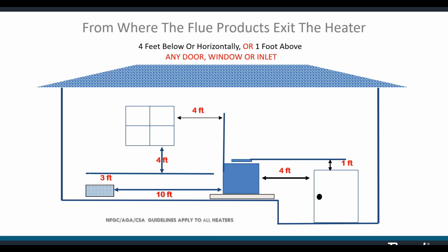When we talk about air, we're mostly talking about indoor installation, but there are some safety issues involved with outdoor installation that have to be addressed. Per National Fuel Gas Code, the point from where the flue gases exit the heater must be at least 4 feet below or horizontal to any door, window, or inlet to a structure. If it's closer than that, the point of exit must be at least 1 foot above. So 4 feet below or horizontally, or 1 foot above any door, window, or inlet. That means if you have a heater anywhere within 4 feet of this window, 4 feet out, 4 feet below, 4 feet to either side, then the top of that heater or the exit point for the flue gases must be 1 foot above the door, window, or inlet.